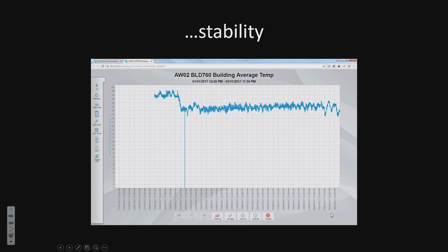Building management system -- so it's the computer controls that are operating those vents, so when the air outside drops down, it needs to know what temperature it is and kick in with some cooling. So ignore this bit, because this is just when they turned it on. You can see the building's sitting comfortably between about 21 and 18, but there's some additional cooling being added in now, because people had forgotten the cooling system in the ceilings was there. So when they turned it all back on after it had been idle, they didn't turn on the cooling, and they've now added some additional cooling. But you can see it's still operating really well.